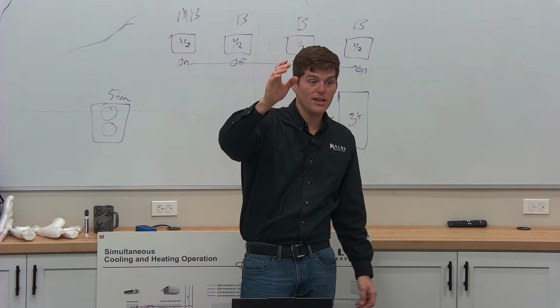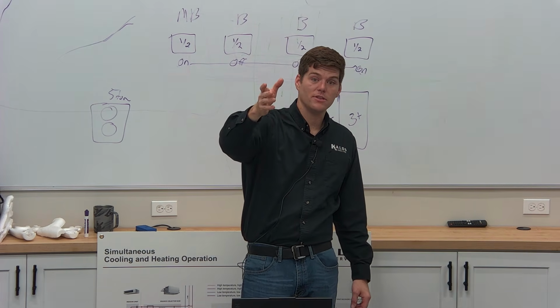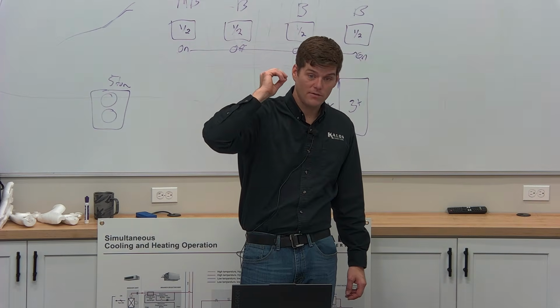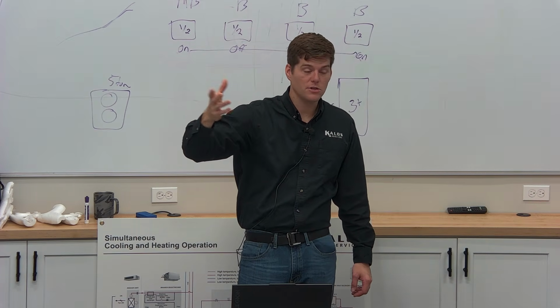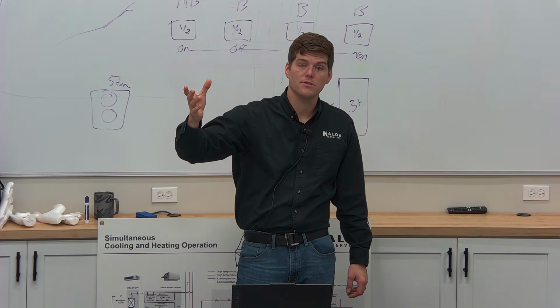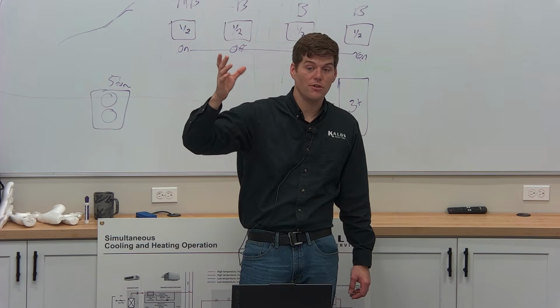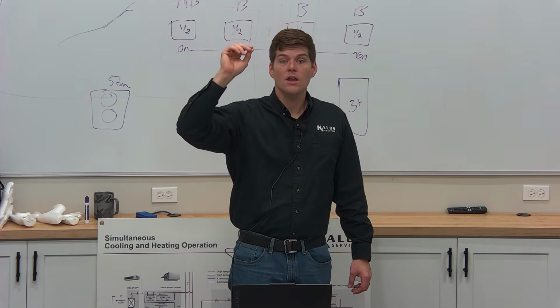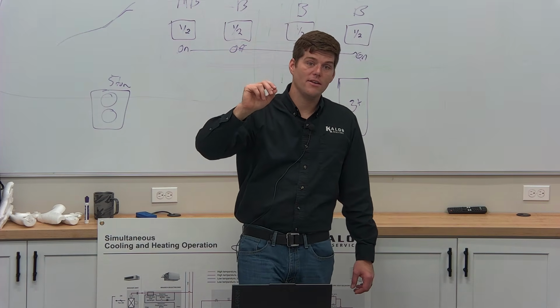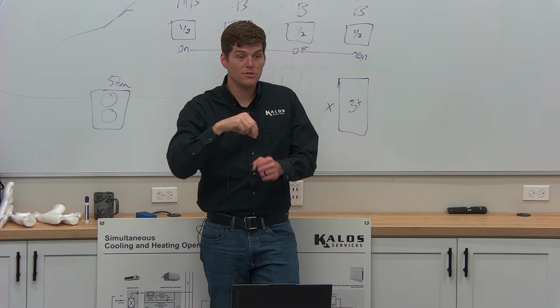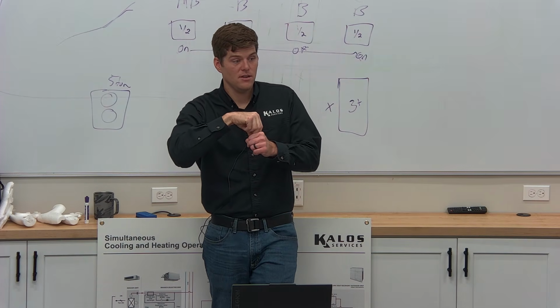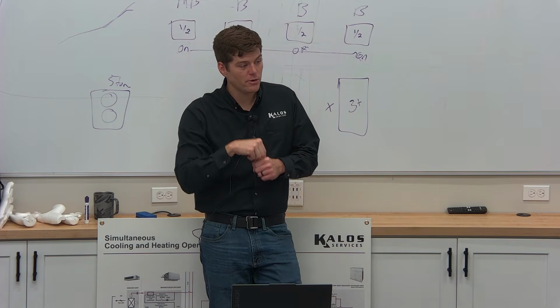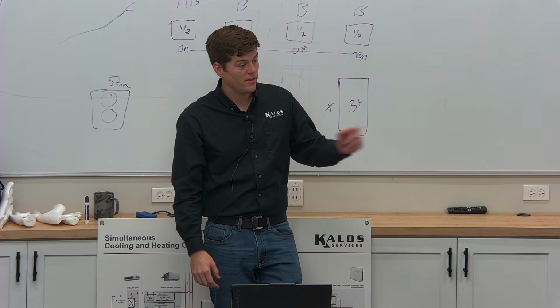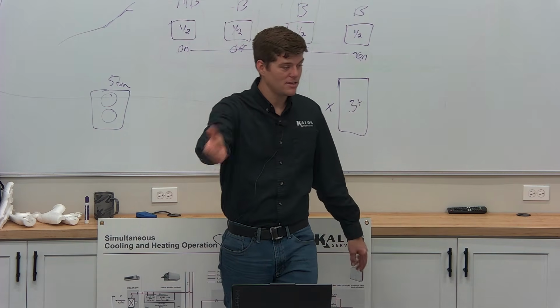When you get dirty, nasty, grimy materials in there that scar that copper flowing through the system, because there are no filter dryers on VRF systems, right? They're just metal strainers, and they don't catch a whole lot. It will actually scar the end of that needle to where when it goes to seat, it doesn't seat all the way. And you get refrigerant leak by. And now you've got liquid refrigerant dumping into a fan that's off, that then makes it back to the suction line, that then makes it back to the outdoor unit.